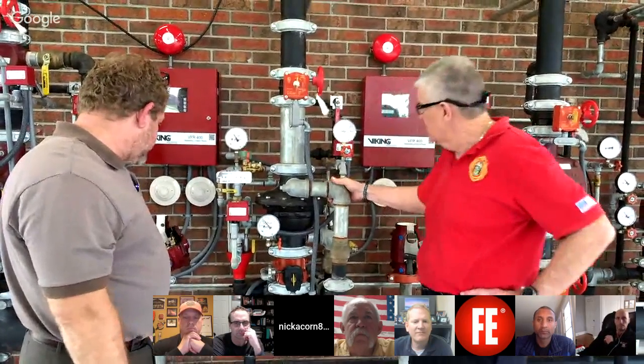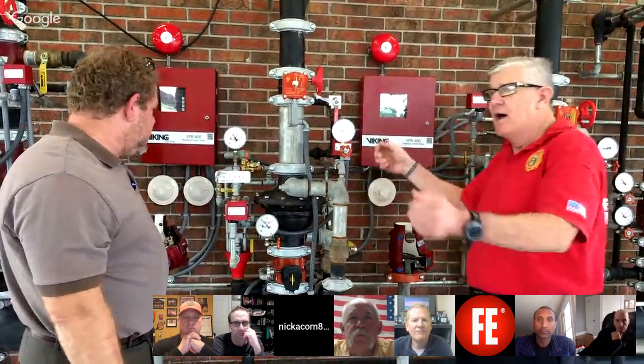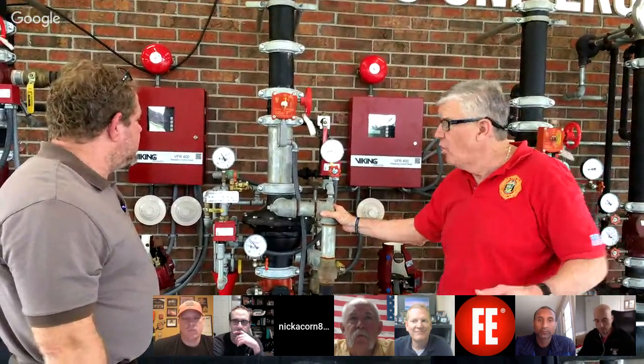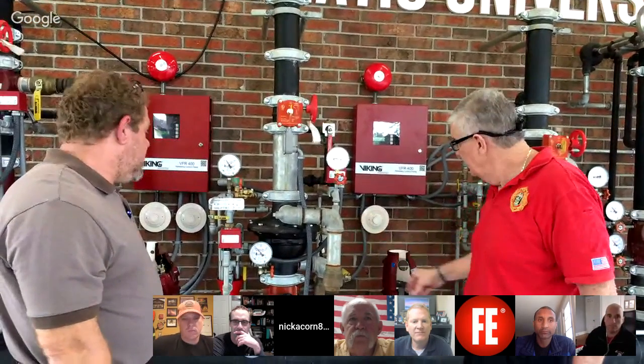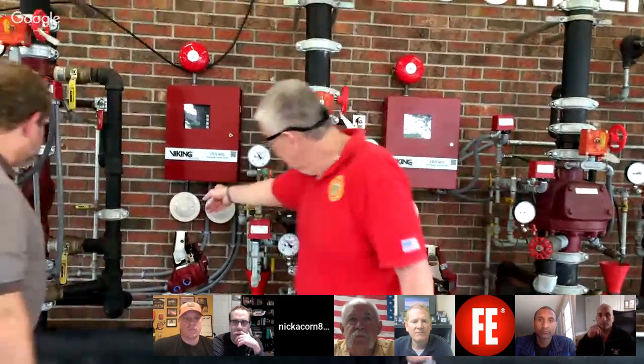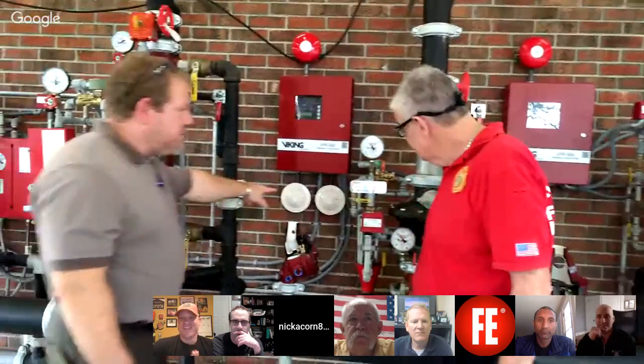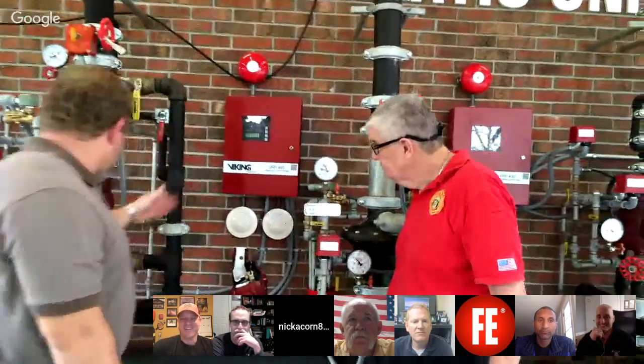With this type of system, this pre-action, I'm driving a forklift and I'm not real good at it, and I hit an in-rack sprinkler. With this type of system, will water flow? Upon release of air, absolutely, water flows. Yep, in a single interlocking. In the single interlock, correct. Now, how about double interlocking? Both forms of detection have to go off before water is released.